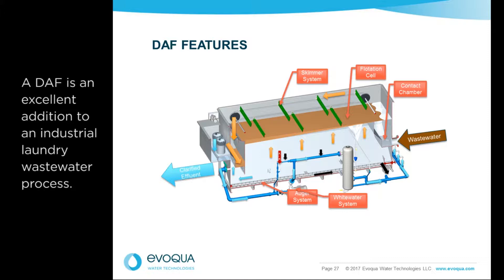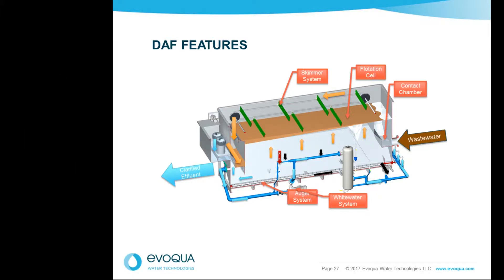Next, there is a flotation cell, which is the surface area within the tank where the bubble-particle matrix floats to the surface and forms a float layer. To remove that floating material, there is a skimmer system — in this case, a flat chain system that pulls material across the surface of the water, drops it into a hopper, and from there it's pumped for either dewatering or disposal.